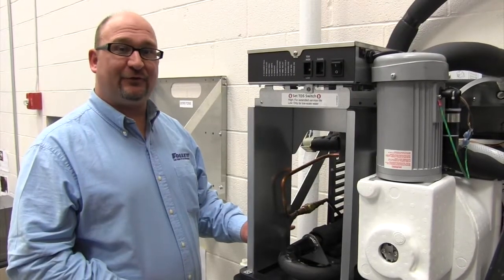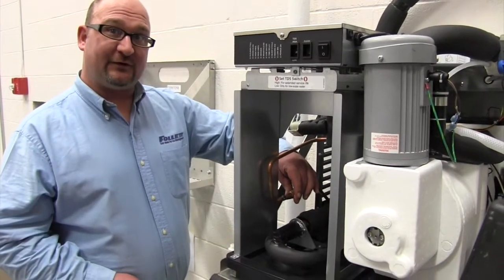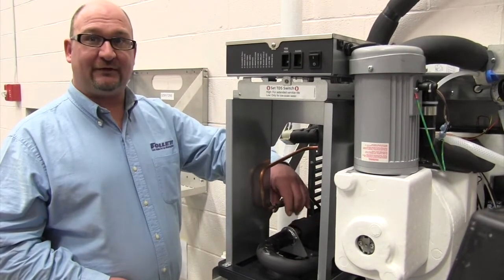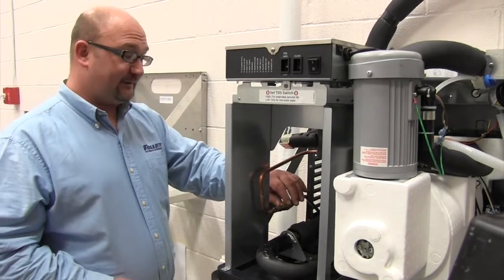The first thing we have to do is take these two refrigeration quick connects off. During the removal of these quick connects, you're not going to lose any refrigerant. You can do it with the system completely charged.